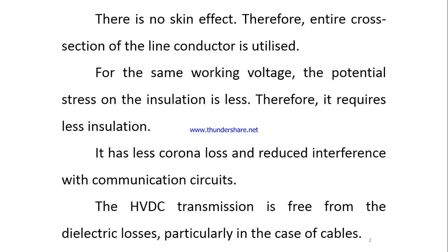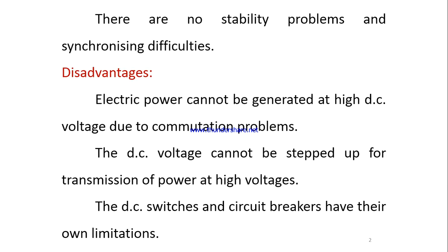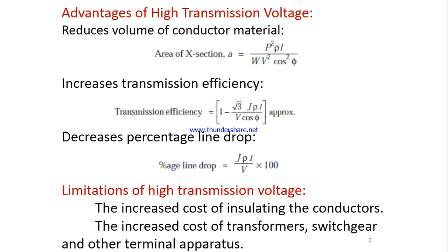For the same working voltage, the potential stress on the insulation is less. Therefore, it requires less insulation. It has less corona loss and reduced interference with communication circuits. So HVDC transmission is free from dielectric losses, particularly in the case of a cable. There are no stability problems and synchronizing difficulties. But the disadvantages are that electric power cannot be generated at a high DC voltage due to commutation problems, and the DC voltage cannot be stepped up for transmission of power at a high voltage. The DC switches and circuit breakers have their own limitations.